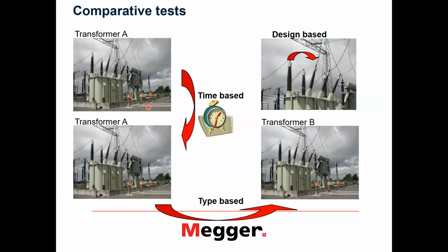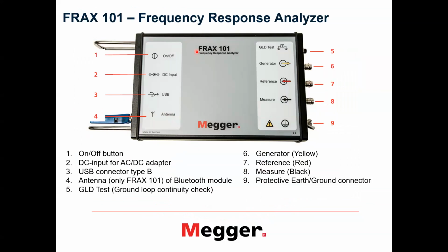And the last case, which is probably the most common one, is that we don't have reference measurements and we don't have a similar transformer with its measurements. So what remains to do is to check how the phases look. And normally when we compare the phases, even if there are certain differences between them, they should look fairly similar. And if we observe, what to say, significant differences, then it means something is wrong. The phases should look fairly similar.